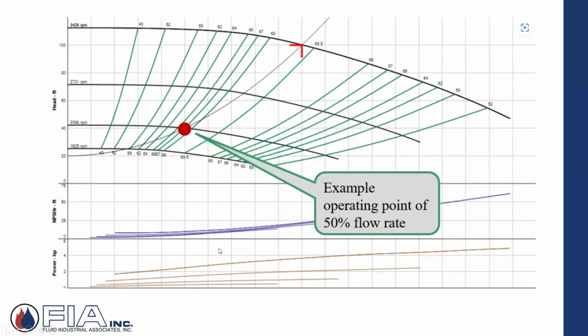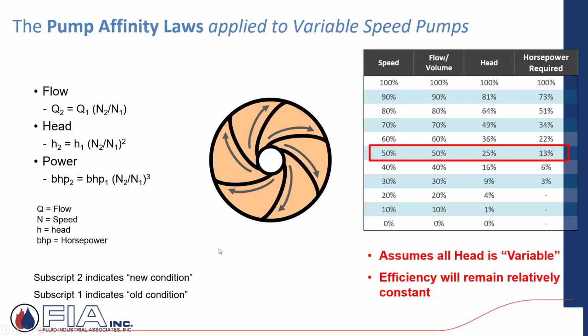And then the variable will be the remaining pressure drop of 80 feet of head, from 20 up to 100, as the head loss changes. Just a visual of the pump affinity laws applied to, in this case, speed. We're not talking change in the impeller diameter. We're just saying change in speed. What's the change in flow? What's the corresponding change in head loss? And then the third column would be our horsepower required.